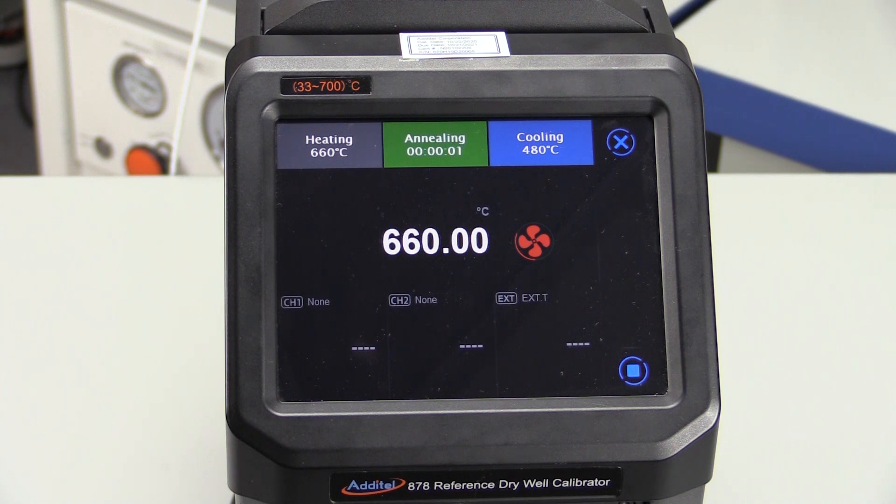As we jump ahead in the process, we can see that the 878-700 will move to the final stage of the annealing process and provide a controlled cooling period. Note that it is important to leave the probes in the 878 as it cools to prevent thermally shocking the probes.